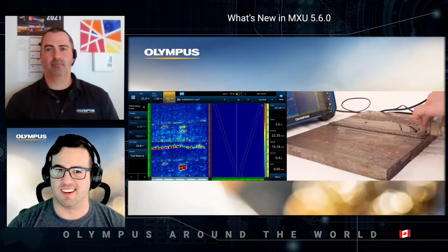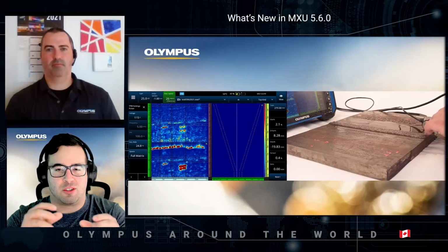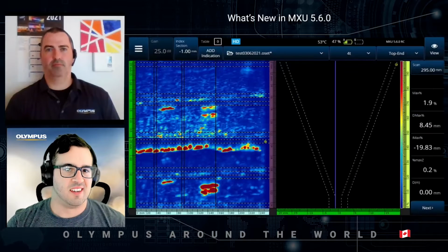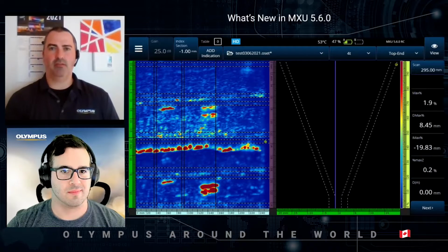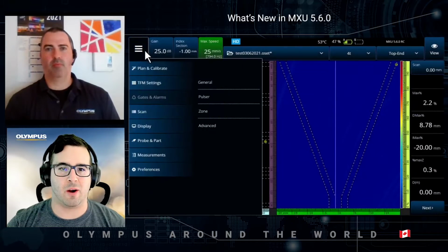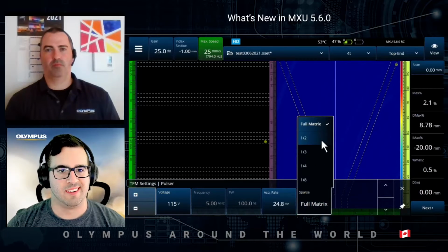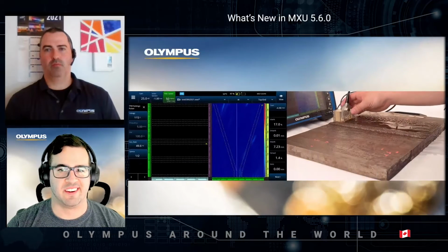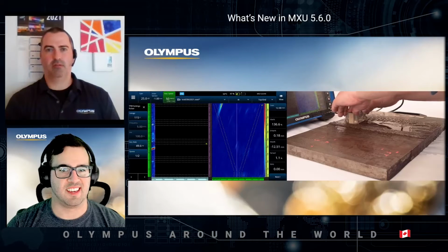But once I scan it, the part here, I try to be as slow as possible. Now you were limited to 25 millimeters per second on this scan. And I will now switch the matrix to 1:2. And that increases the speed of the acquisition rate. Basically doubling it.